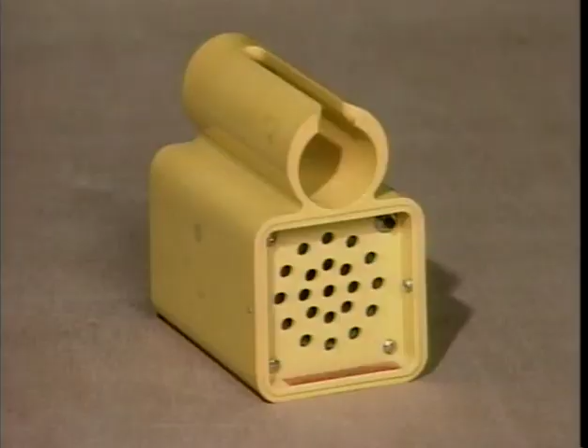Now, the first tester we'll look at in detail is a noisy tester. A noisy tester uses sound to indicate the presence of voltage. This tester consists of a molded case with a slotted tube and a test button, which is located on the bottom of the case. Before using the tester, you should inspect it to make sure it works properly. This particular tester is battery operated. You check the battery by pressing the test button. If the tester sounds, the battery is in good condition and the tester can be used.